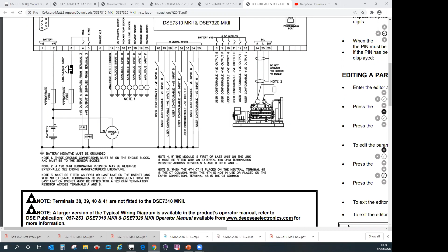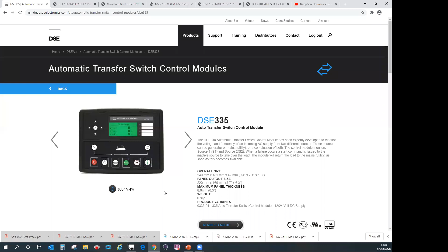Can the ATS controller switch between supplies without power failure? I think what the question really is, if we go back to one of our ATS range controllers, let's pretend we've got a generator on S2 and a main supply on S1. If mains fails and the generator's got to start and go on load, in that period of time the site is going to have no power going to it whatsoever, and that could mean the ATS has got no power going to it as well. That could mean this controller then switches off. But in its default state, it's still sending the output to the generator to start, so the command is still there for the generator to start. Once the generator starts and closes its breaker, this should hopefully come back online.